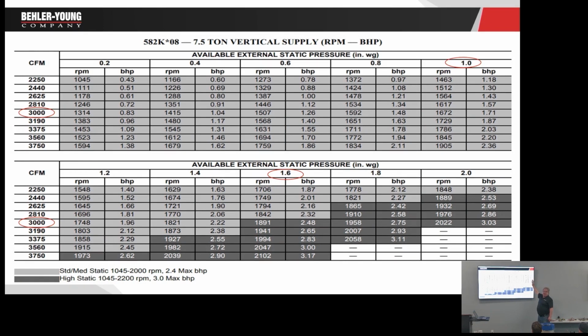So what happens if I have over 1 inch? I'm no longer moving enough air, and now the blower is going to be cutting out. Anybody ever have a blower wheel blow apart or seen it? That's usually what does it. I got a standard static unit and I get too much static on it. Airflow issues. If I'm having airflow issues, coil's frosted up, limit keeps tripping.